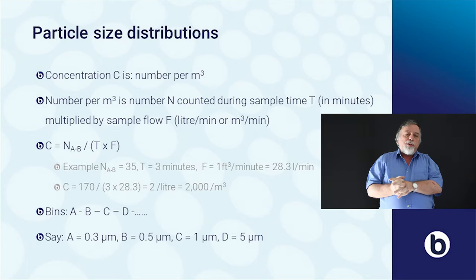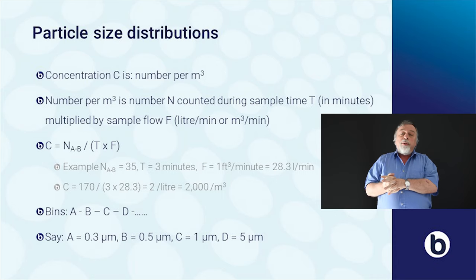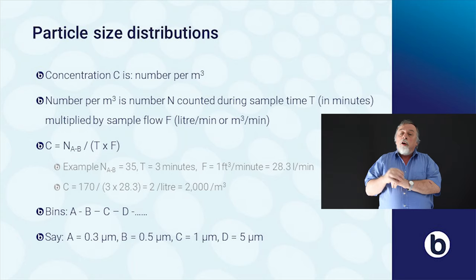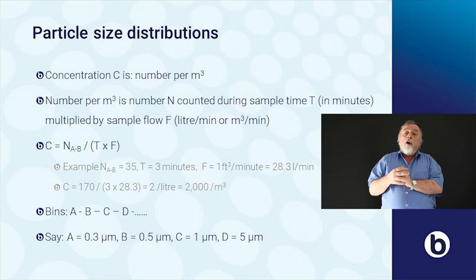Here is a small example: the number of particles counted between A and B is 35, the time is 3 minutes, and the flow is 28.3 liters per minute — one cubic foot per minute. If we calculate this, we find the result of 2 particles per liter of air, or 2000 particles per cubic meter.